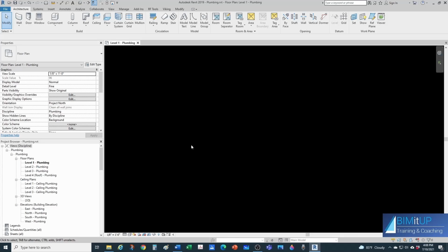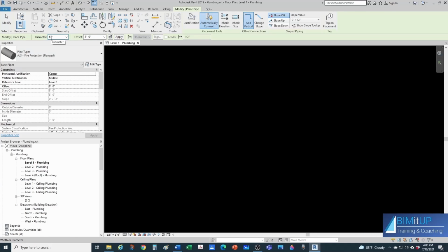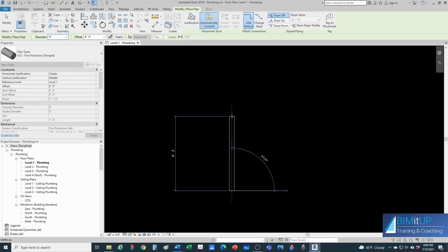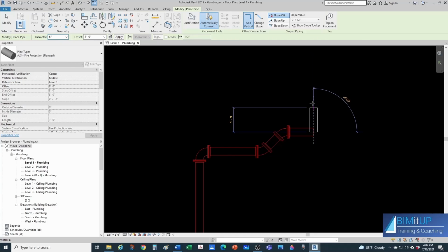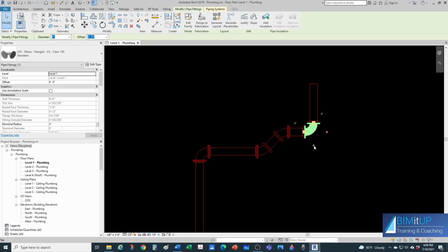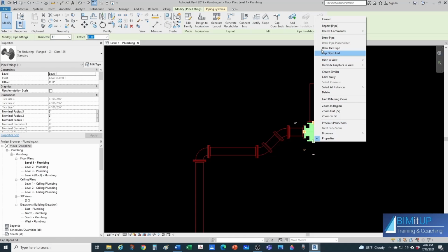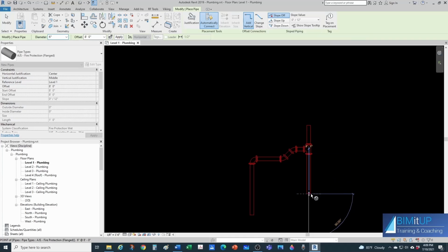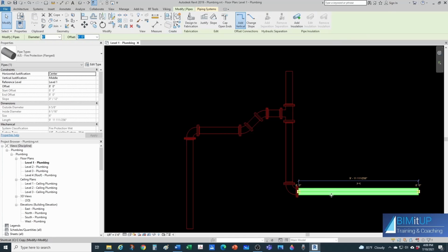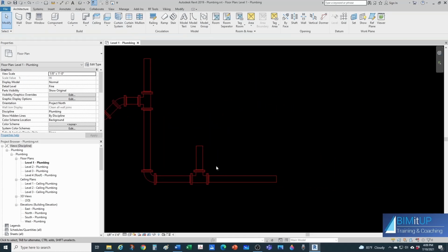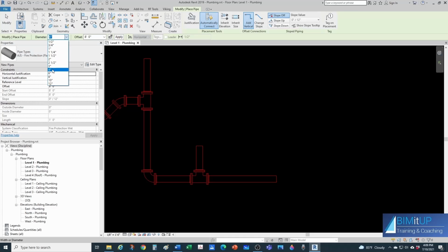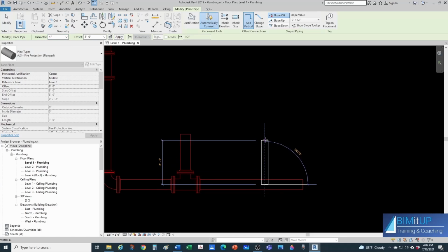Okay, so first I'm going to show you the final product. So let's draft the pipe. I'm using a 6-inch steel pipe, and my pipe type is called, in this case, AJS, which is my initials, Fire Protection Flanged, because I use this one for fire protection. So you want to be able to do 90 degree elbows, 45s, and then you should be able to upgrade a fitting from an elbow to a T. And say you want to pop off with a T with a 6-inch pipe here, you should be getting a flanged T. And then at the same time, if you want to do a 4-inch, for example, you should be able to get a reducing T.